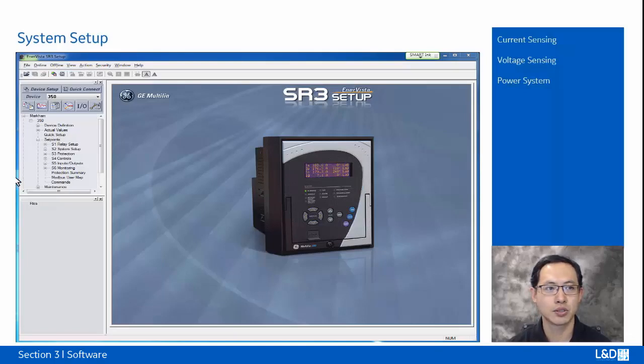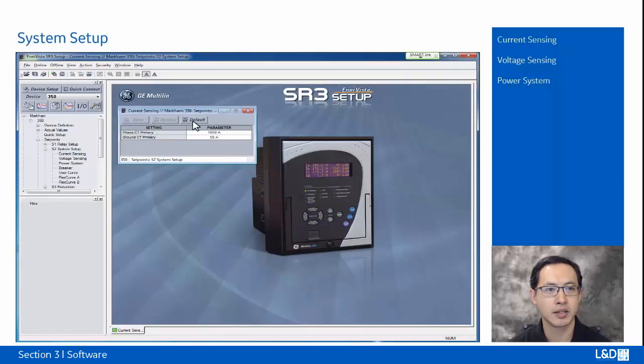So to set up the CT, we go to the system setup and click current sensing. And here we can see the CT primary current, and we have 3 ways to change this setting. The first one is by clicking the cell and using the arrow keys to press up and down to change the values. The second way is to click this enter key, start the keypad, and use the keypad to type new values and press the equal sign.